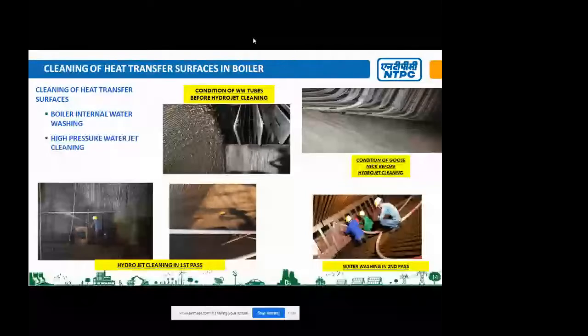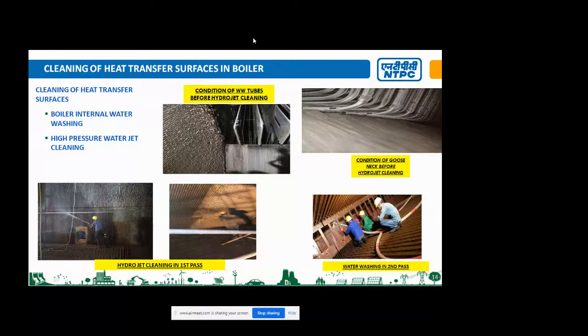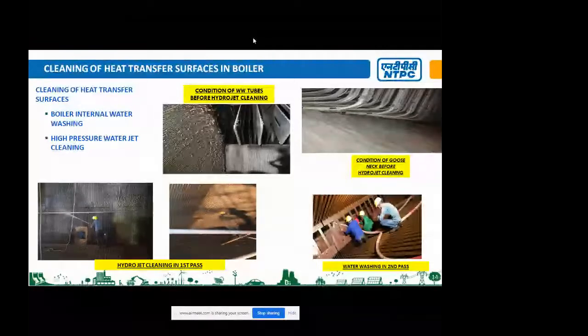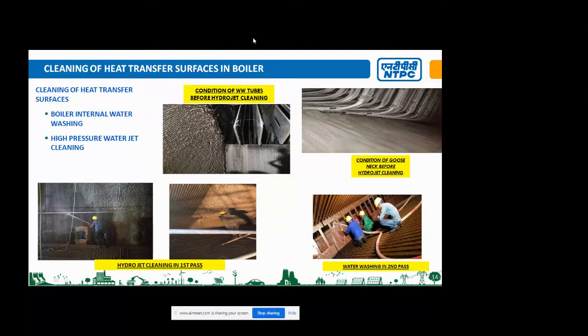Sir, is it visible, cleaning of heat transfer surfaces? Yes, absolutely. Please go ahead. And a quick reminder that we have 15 minutes left for the session. Yes, sir. As we know, we have very big boilers. So at every opportunity or in the overhaul, we thoroughly clean the heating surfaces to increase our boiler efficiency. It is our observation that nearly about 1% boiler efficiency increases by cleaning these boilers, including the air preheater. We are replacing our air preheater basket every 6 years, and every year we thoroughly clean with high pressure jets to improve our boiler efficiency.